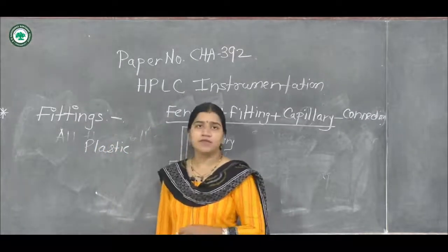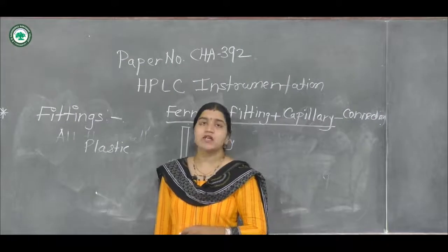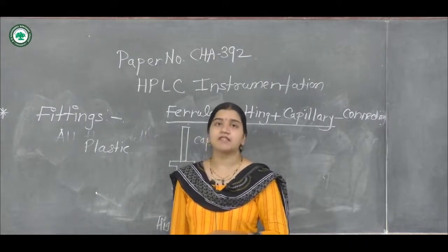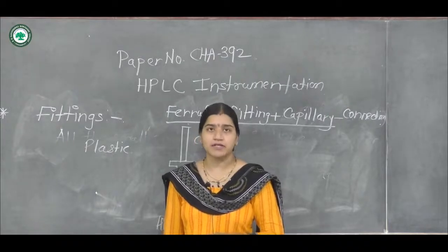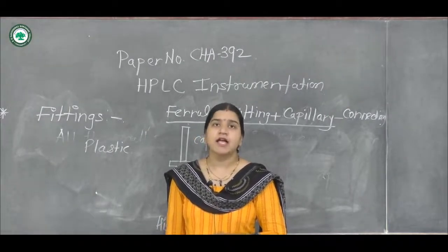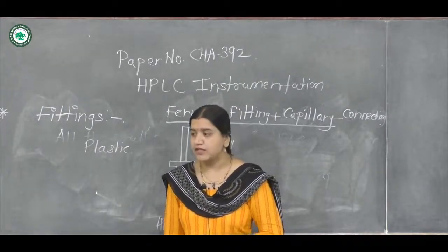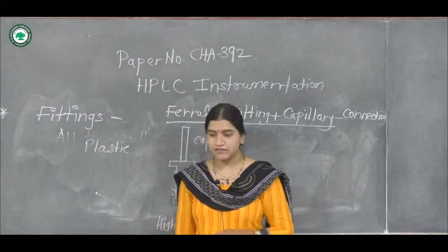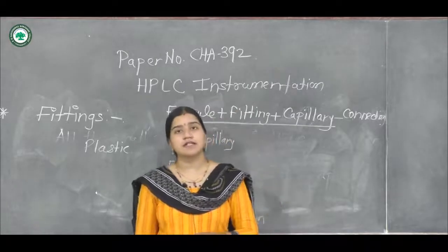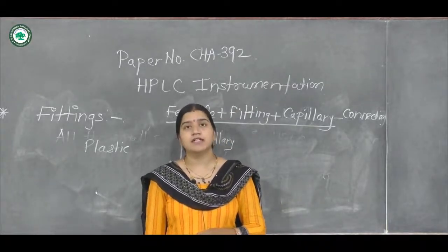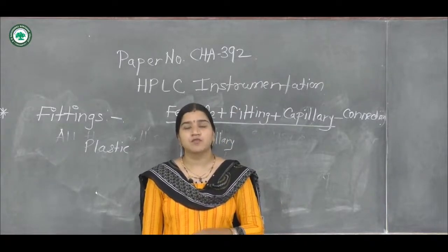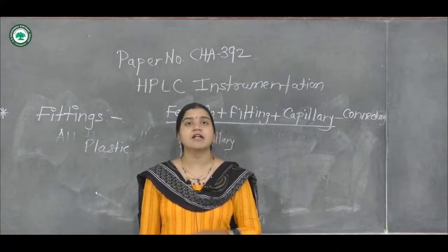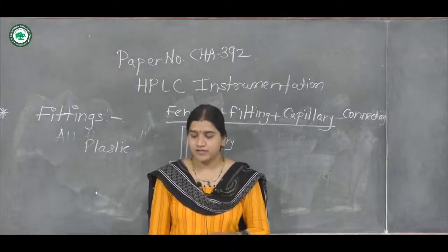Why are the plastic fittings most widely used? Because plastic is a chemical resistant material as well as a corrosion resistant material as compared to the steel. And one more advantage is that the ferrule can be separated from the fitting in case of plastic fitting, while in case of the stainless steel fittings the ferrule is directly attached to the fitting. So this is the main difference between the plastic fitting and the stainless steel fittings.